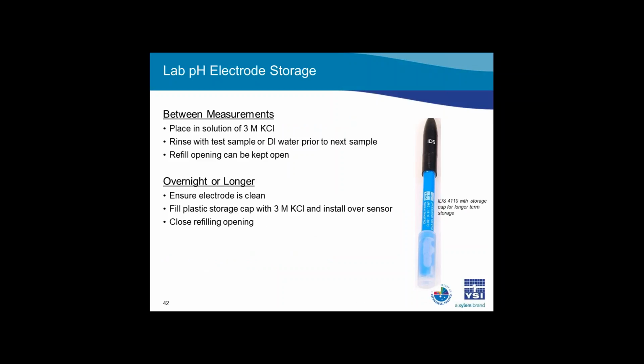When storing lab electrodes between measurements, place the electrode in a 3 molar potassium chloride solution. Be sure to rinse the probe with some sample or DI water before placing it back into the sample for measurement. So after you pull out of storage, make sure you rinse it before you put it into a sample. You don't want to carry over any KCl into your sample. Also, as we have mentioned before, make sure the refill hole is open during measurements. If you are storing your lab probe overnight or longer, make sure it is clean, and then fill the storage cap with 3 molar KCl and install it over the sensor. Be sure to close the refill hole during storage so the electrolyte does not evaporate during storage time.